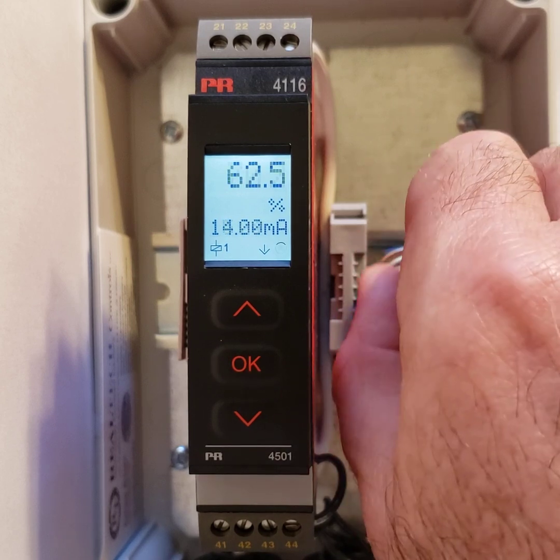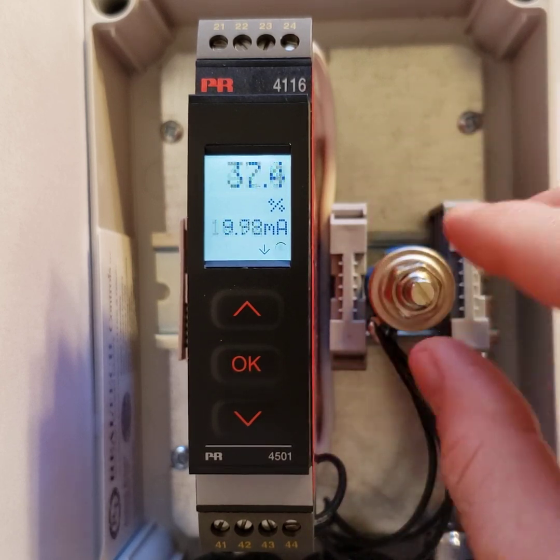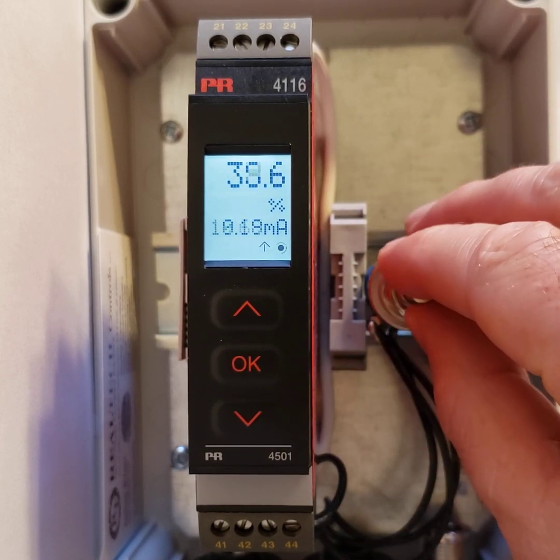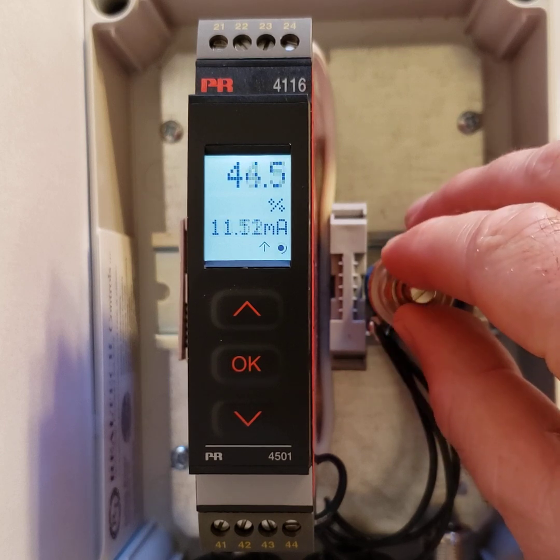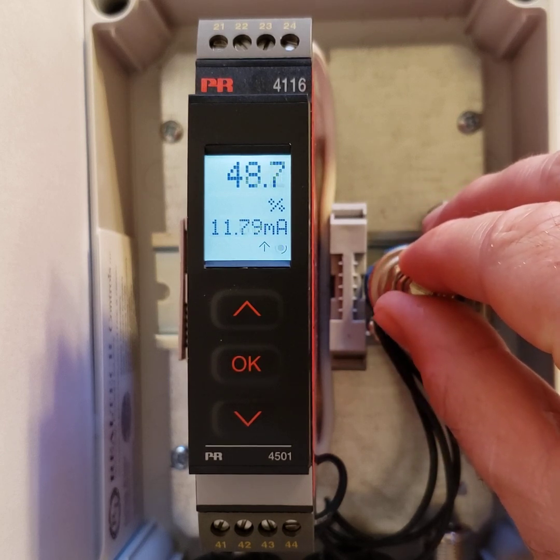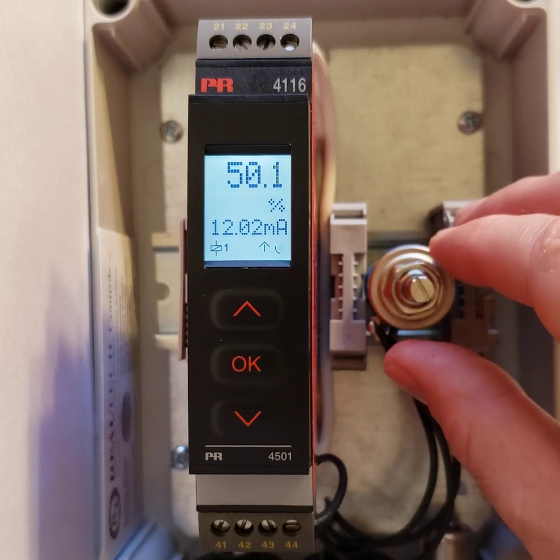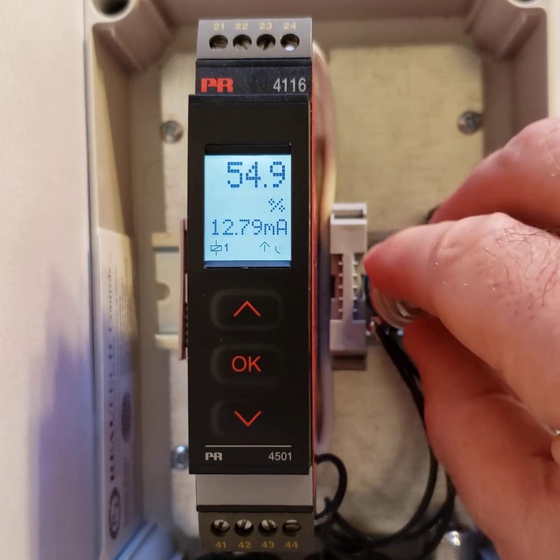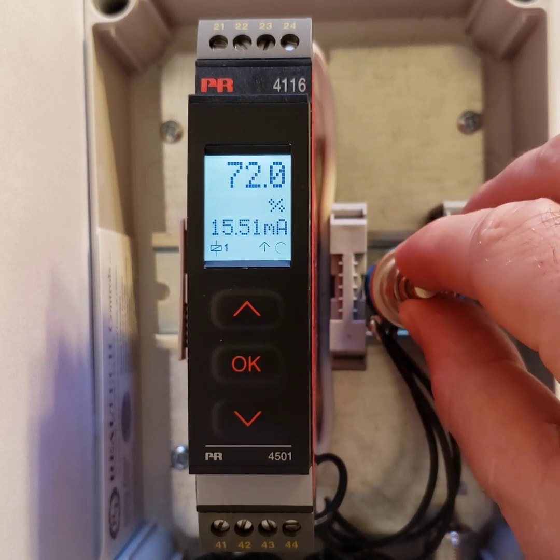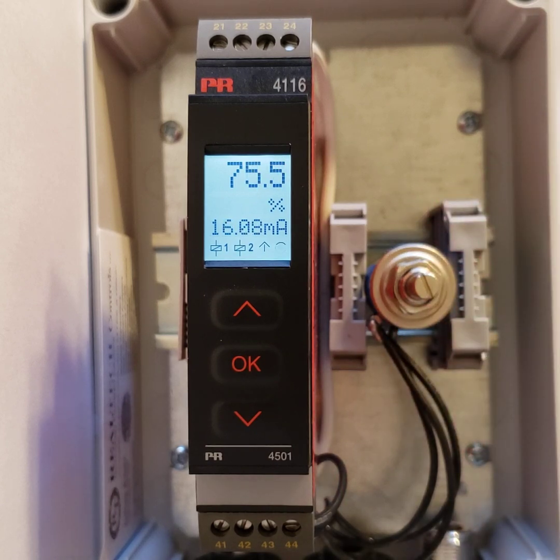I have relays, as you can see, turning on and off over there. The first relay, number one, is set at 50%. So as I scroll past 50, my relay one turns on. And as I scroll past 75, relay two turns on.